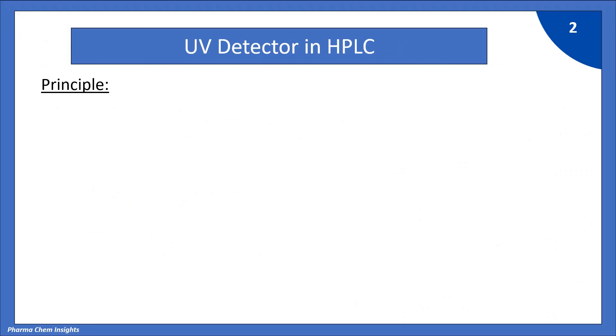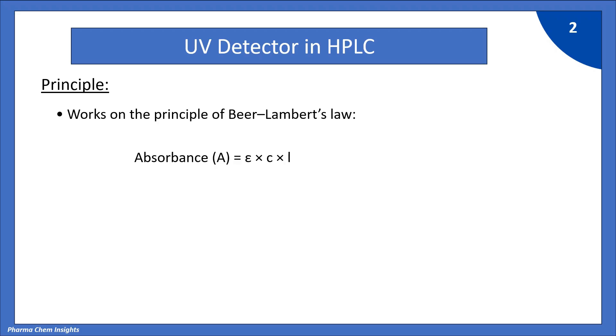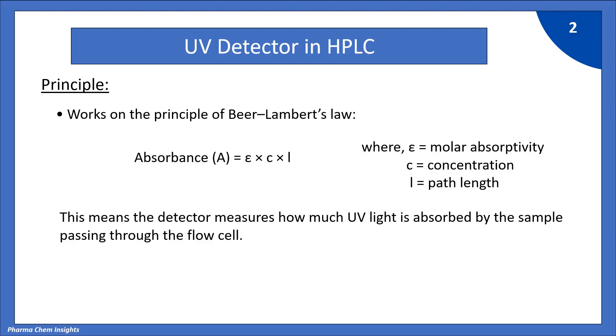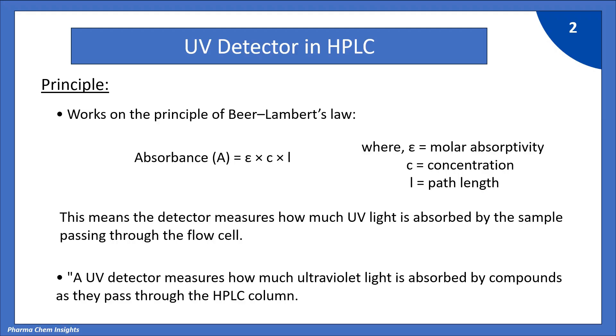Let's first see the principle of UV detector. It works on the principle of Beer-Lambert's law, where absorbance A is equal to Epsilon into C into L, where Epsilon is molar absorptivity, C is concentration, and L is the path length. This means the detector measures how much UV light is absorbed by the sample passing through the flow cell as compounds pass through the HPLC column.